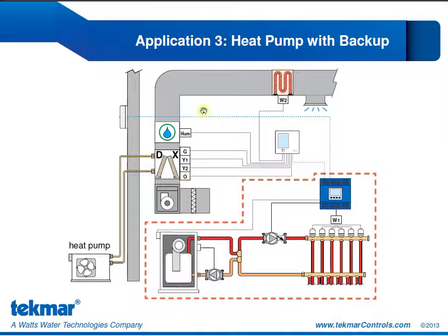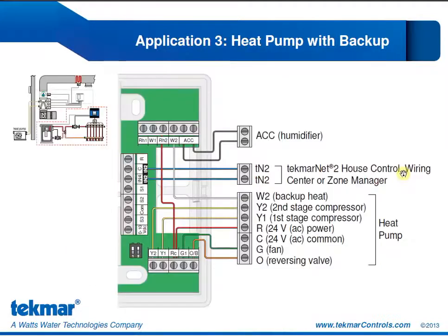When we're in cooling mode, we have up to 2 stages of cooling with the Y1 and the Y2. And in this case, we would power the O for the reversing valve. Notice we have a humidifier in the ductwork that is going to be controlling our relative humidity.